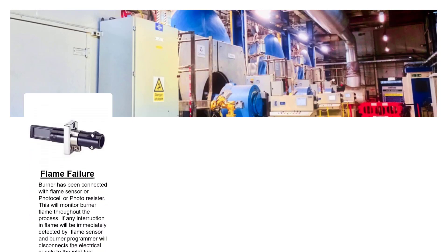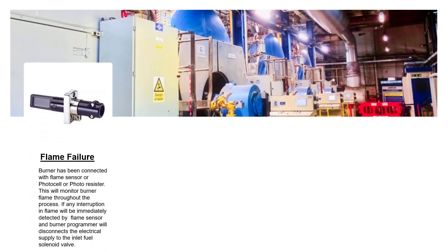Let's discuss electrical safeties one by one in detail. Flame failure: the burner is connected with a flame sensor, photocell, or photoresistor. This will monitor the burner flame throughout the process. If any interruption in the flame is detected by the flame sensor, the burner programmer will disconnect the electrical supply to the inlet fuel solenoid valve.